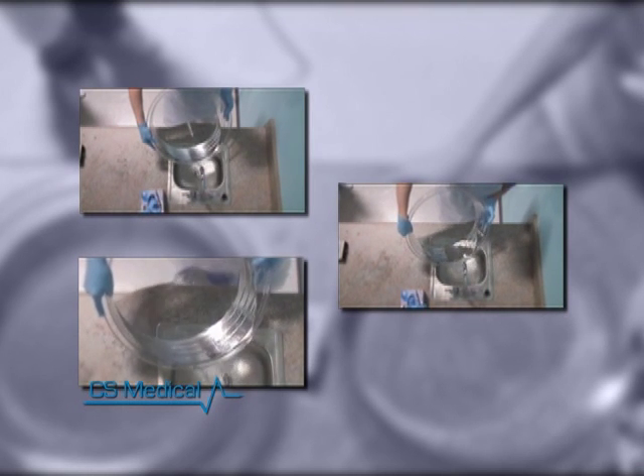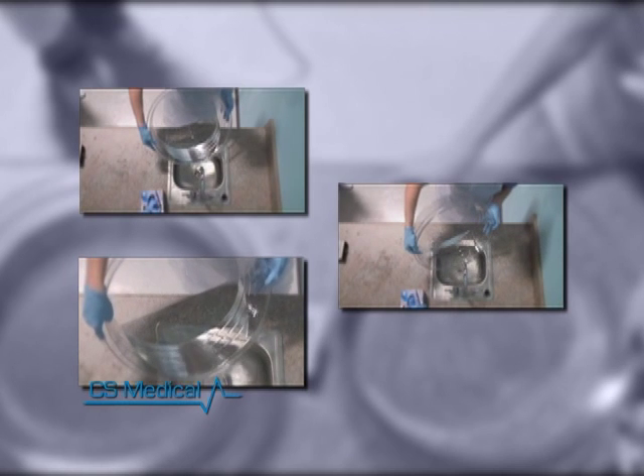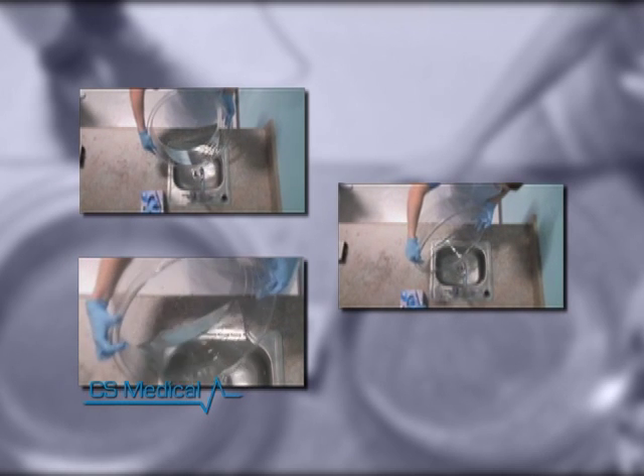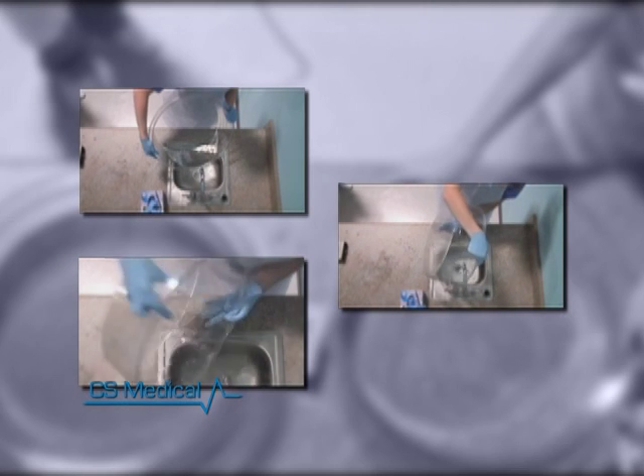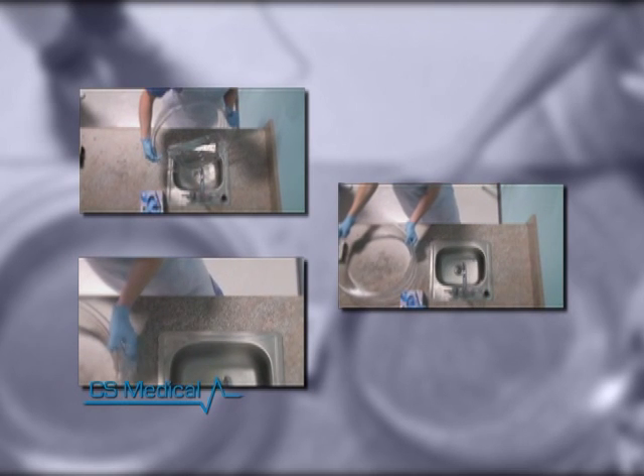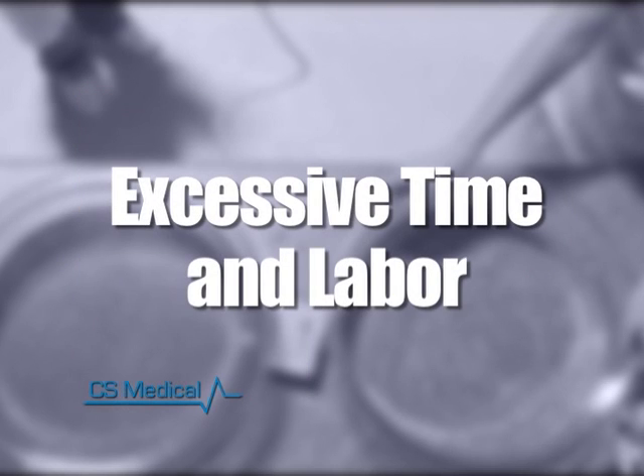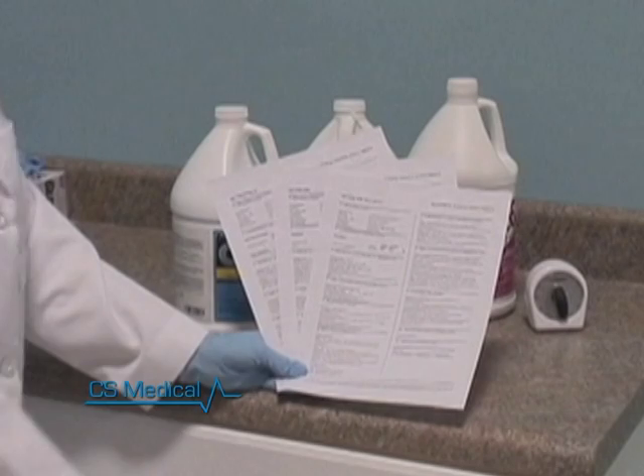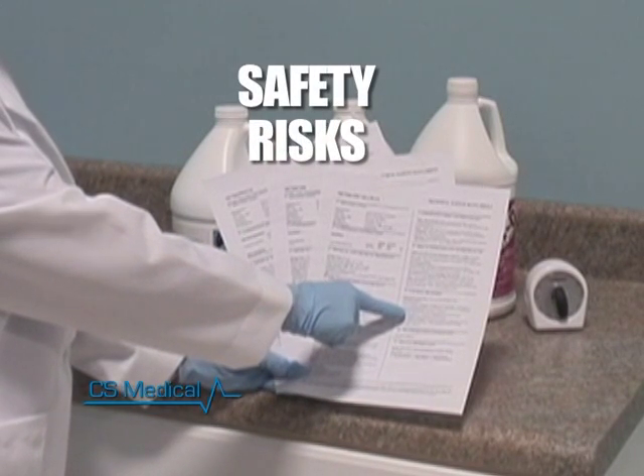Plus, you have the issue of high-level disinfectant and how to dispose of it. You must neutralize the disinfectant before dumping it down the sink drain. This adds yet another bowl of liquid you must maneuver. In addition to the excessive time and labor required to manually reprocess the TEE probe, you must be aware of the safety risks of glutaraldehyde or OPA.